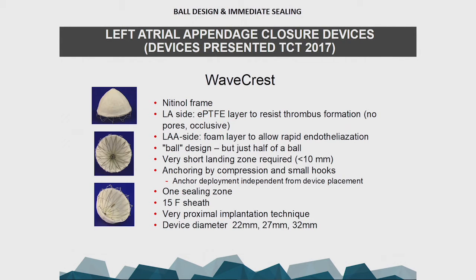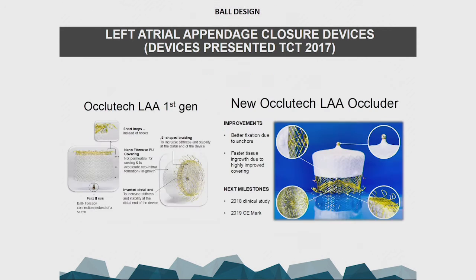And the concept of the device is to allow an occlusion without the use of echo. So you can implant a device, it occludes immediately the LAA, it has a tissue that doesn't have any pores. Once you have the device in place and it's not released, you can inject contrast, and you can see if you have complete occlusion of the LAA. And if you have good positioning and you have excluded leaks, you can then release the device.